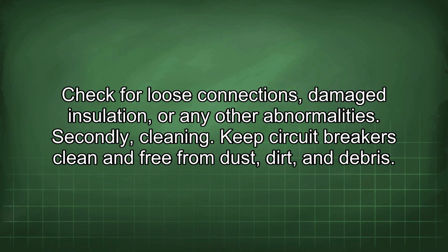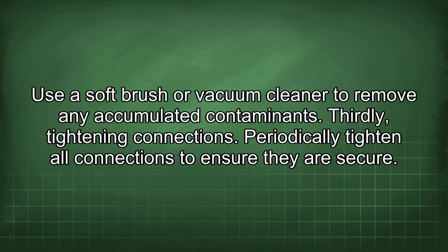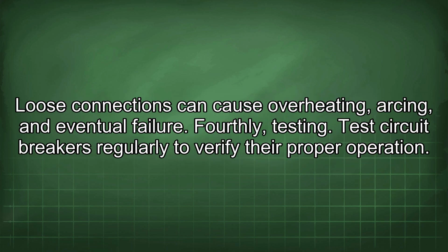Secondly, cleaning. Keep circuit breakers clean and free from dust, dirt, and debris. Use a soft brush or vacuum cleaner to remove any accumulated contaminants. Thirdly, tightening connections. Periodically tighten all connections to ensure they are secure. Loose connections can cause overheating, arcing, and eventual failure. Fourthly, testing. Test circuit breakers regularly to verify their proper operation.